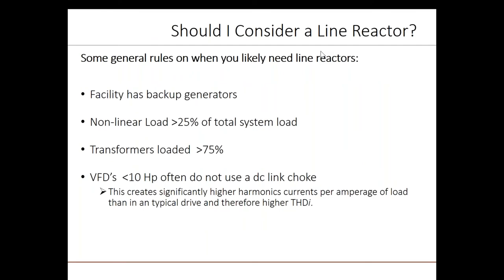Here are some other reasons to consider a line reactor. Backup generators have to be sized to supply not only the motor load, but the additional harmonic currents. By reducing current harmonics, line reactors may reduce the load enough to allow sizing of a smaller and less expensive generator. If the nonlinear load exceeds 25% of the system load, line reactors should be considered. Next, if transformers are heavily loaded above 75% for extended periods, harmonics can cause dangerous heating. Line reactors should be used to reduce this heating. Lastly, since small VFDs do not usually have a DC-link choke, it is worth considering using a line reactor on these small VFDs.